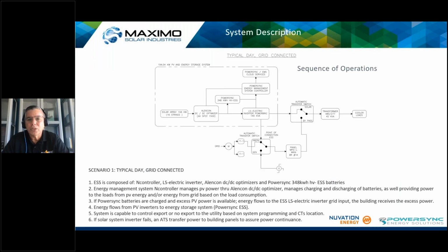This is the sequence of operation for the grid-connected system. You can see the Powersync batteries, the energy management system, and the 348 kilowatt-hour high voltage battery, and it's connected to the DC bus through the solar array and the Alencon optimizers. Like I mentioned before, the optimizers in this case are also MPPT, maximum power point trackers. The system is a 1500 volt system, so it's a really high voltage application. And then we have the LS Electric inverter, 140 kilowatts. These equipments are great because you can build the same system modularly and parallel many of these systems to get the design that you want, whether it's 1 megawatt, 2 megawatt-hours, or 1.5 megawatt, 2.5 megawatt-hours. It's pretty much the same design.